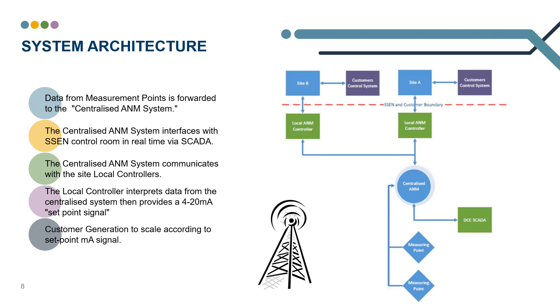Now I'm going to talk about how we get this information from the measurement points to the generators. The measurement points are fitted with communications equipment, and this data is forwarded to our cloud based centralised ANM system. The centralised ANM system interfaces with our control room in real time via SCADA and also communicates to the local controllers that are based on site. These local controllers on each individual site interpret the data from the centralised system and then provide a 4 to 20 milliamp set point signal which is sent to the individual site. The customer generation should then be capable of scaling according to this milliamp signal.